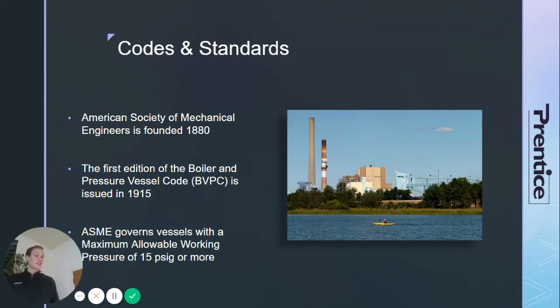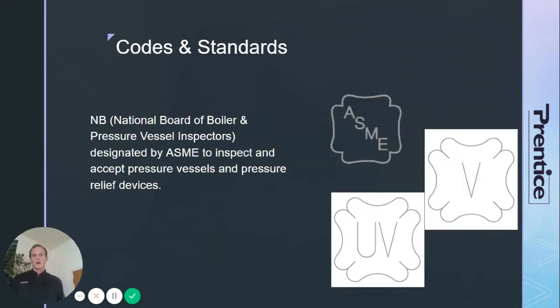ASME only governs vessels with an MAWP of 15 pounds gauge or more, so we'll talk about how industry fills in the gaps for vessels and devices below that pressure. ASME writes the rules, but they don't do the field work — they've designated the National Board of Boiler and Pressure Vessel Inspectors to inspect devices and vessels like boilers.